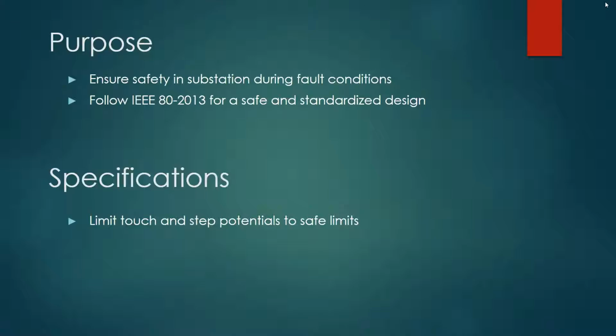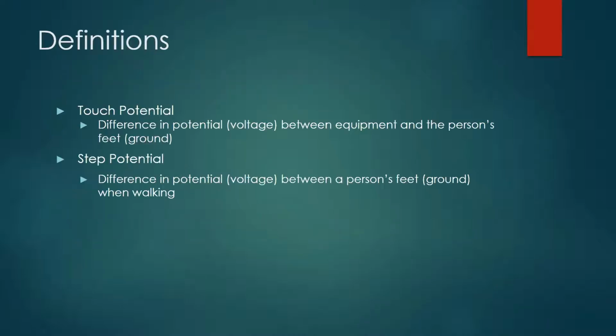The purpose of a grounding grid is to ensure safety in the substation during fault conditions. We designed ours to follow IEEE standard 80-2013. For specifications, we want to limit touch and step potential. Touch potential is going to be the difference in potential between equipment and the person's feet when they're touching the equipment, while step potential will be the difference in potential between a person's feet when they're walking through the substation.